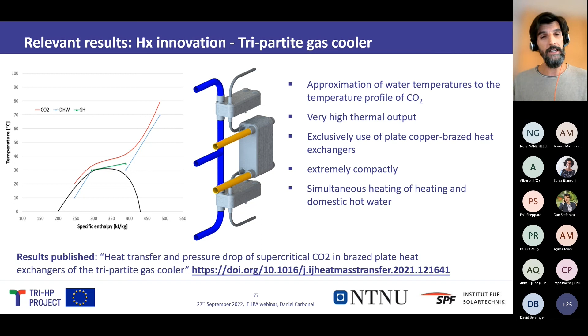So basically, in these heat exchangers, you see on the bottom part, it's what we are using for preheating water. In the graph on the left, you can see the blue line going from 10 to maybe 30 degrees. Then we go in with another heat exchanger, the middle one, for space heating. This is heating water from 30 to 35. And then the last heat exchanger takes the preheated domestic hot water and reheats it from 35 to 60, 70 degrees. With this, the efficiency of the heat pump for space heating and domestic hot water is very high, and we can use it also for space heating applications. Also here you can see the publication on the experiments of this tripartite gas cooler.